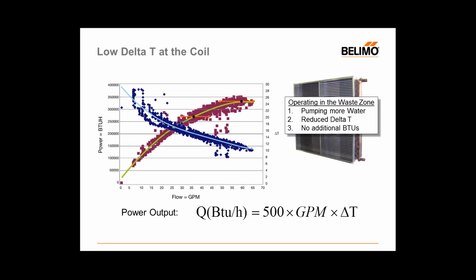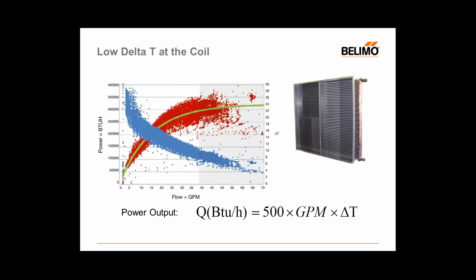What you're actually looking at on this graph is some data from a constant air volume coil on an air handler, and it's a very clean, well-knit data set. But if we take a look at something that's a little bit more typical and a little sloppy in terms of our heat exchange, like the one I've just popped up here on the screen, now we can take a look at a partial load point and extrapolate a line horizontally. And now you'll see that even at this partial load, there's an enormous range of flows that were utilized.